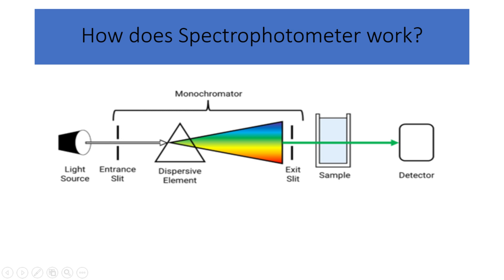The transmitted or scattered light from the sample is collected and directed onto the detector. The detector converts the light into an electrical signal, which is then processed by the signal processor. The processed signal is displayed or outputted, providing information about the intensity of light at the specific wavelength, which reflects the quantity of the compound of interest.